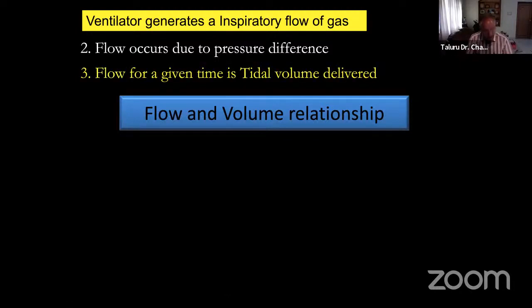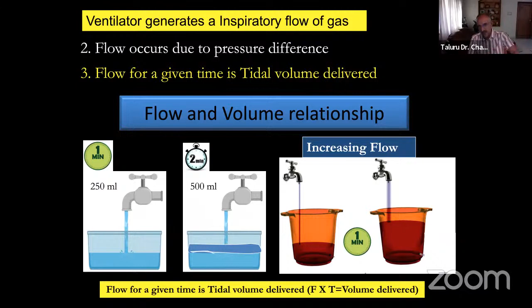This is where the understanding has to be there, especially in pressure support ventilation, which is the mode we use in the ICU almost 70 to 80% of the time. There is nothing you can alter. The I:E ratio cannot be altered. The patient controls the rate. Only tidal volume we control, by altering the pressure support. And the only way we can alter the inspiratory time is by altering the rise time, that is, increasing the peak flows, or shortening the inspiratory time by altering the expiratory trigger sensitivity. This is the understanding that you should have.